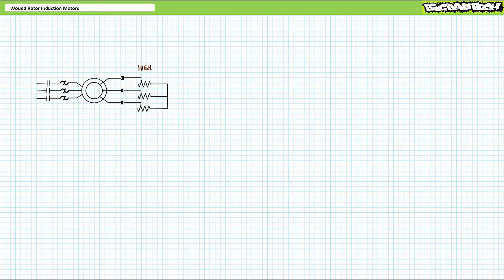Alternatively, rather than making use of fixed secondary resistors switched in and out of the circuit, consider an adjustable external resistor bank. This allows an operator to vary the resistance of the rotor circuit in an analog fashion, as opposed to a digital full on or full off manner.